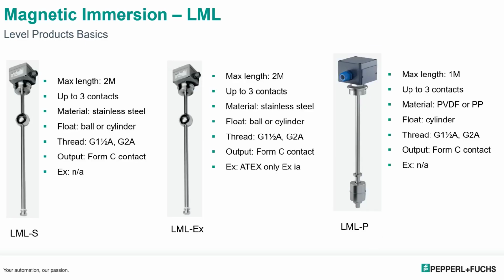We have 3 different versions of the LMLs. The LML-S is a basic version, not intrinsically safe and not for hazardous locations. Max length is 2 meters. You can have up to 3 contacts in this unit. The rods are stainless steel. You can get this in a ball or cylinder, just like the float switches. The ball floats on the surface easier than the cylindrical type units. Then you can get them in different threads. Right now we show G1.5 and G2 threads, but they also come in NPT threads as well. And you can get this in a Form C contact output.